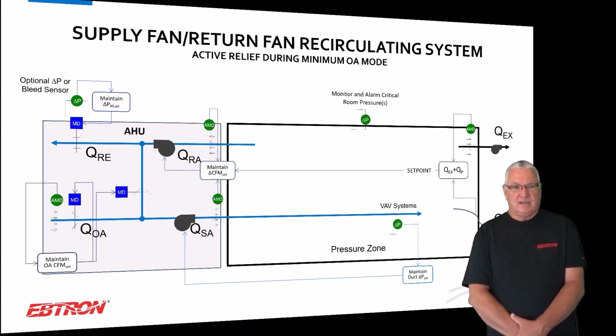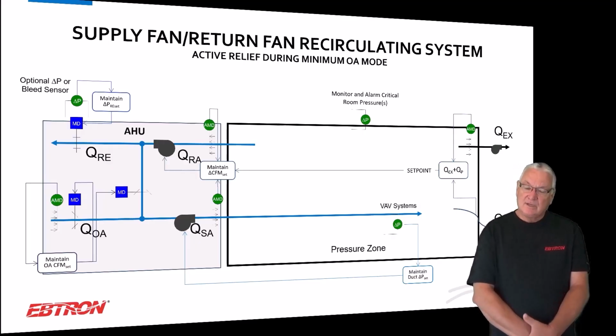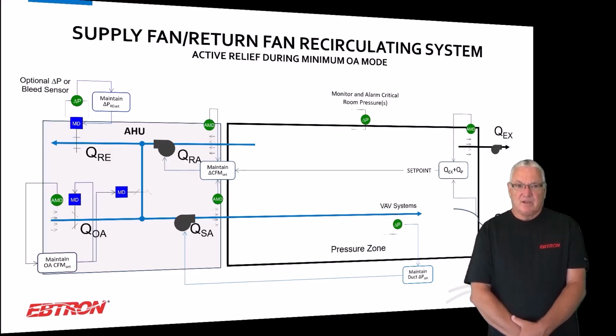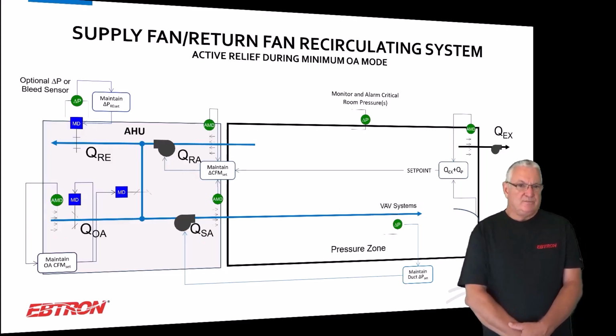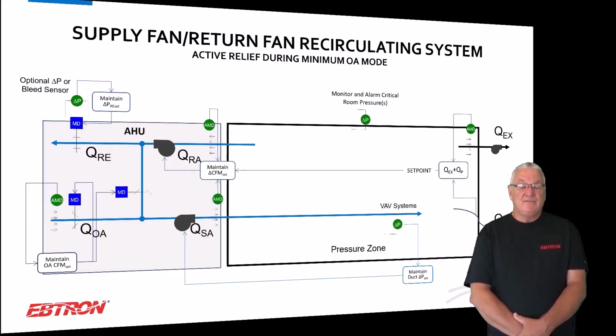We're using the outside airflow station. We're using the outside air damper and the recirc air damper to maintain set point, because that set point is higher than the differential. Okay, and you're using the supply and the return airflow differential to control the return air fan, and you can just go to position really on the outside air. I mean on the relief air.